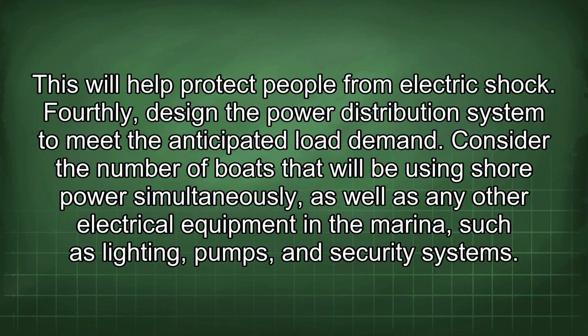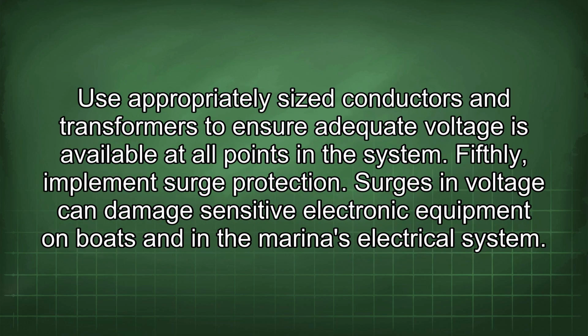Fourthly, design the power distribution system to meet the anticipated load demand. Consider the number of boats that will be using shore power simultaneously, as well as any other electrical equipment in the marina, such as lighting, pumps, and security systems. Use appropriately sized conductors and transformers to ensure adequate voltage is available at all points in the system.